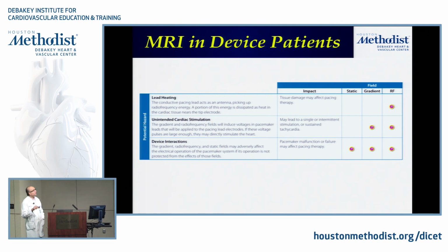And again, this was due to both the RF pulses that are applied as well as the gradients that are switched on and off. And then lastly, there was a concern for device interactions that are thought to be due to both the static magnetic field, due to the gradients, as well as the RF. And the concern could be that there could be pacemaker malfunction or failure that may affect pacing therapy.